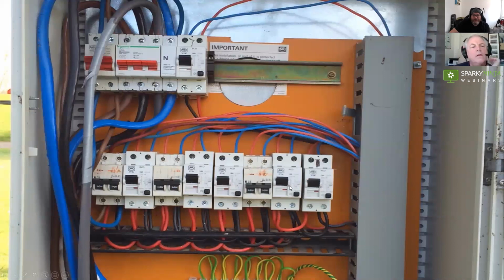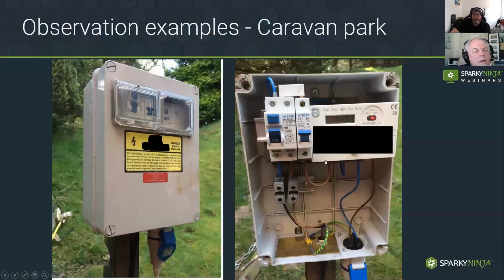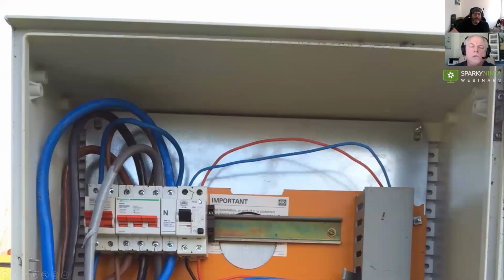Right. Because there's no overcurrent protection in there, and there's no overcurrent protection in that. So the overcurrent protection for these cables on these RCDs going under the ground is basically relative to the overcurrent protection for there. So the only thing you could loosely say is, okay, is overcurrent protection needed if the demand is going to be no more than 16 amp here? Does that afford overcurrent protection because it's in line for these cables?